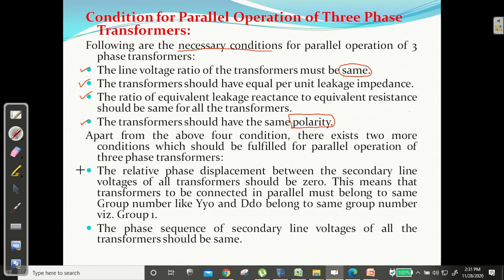The next condition is that the relative phase displacement between the secondary line voltages of all transformers should be zero. This means transformers to be connected in parallel must belong to the same group - for example YY0 and DD0 can be connected in parallel. Group number 1 will be connected to group number 1, group number 2 will be connected to group number 2, and so on.